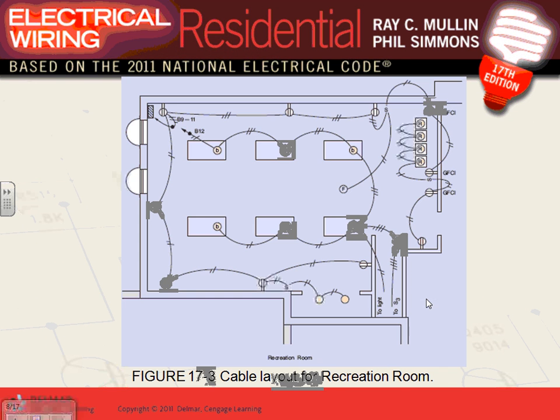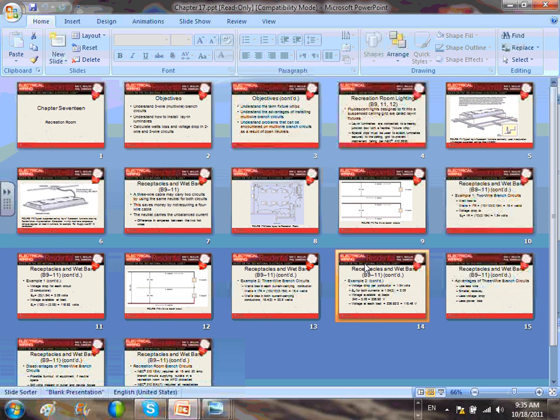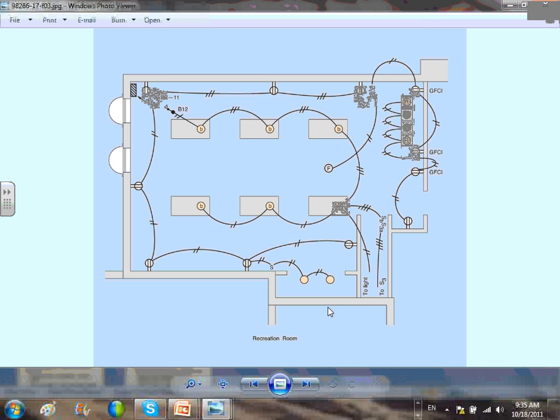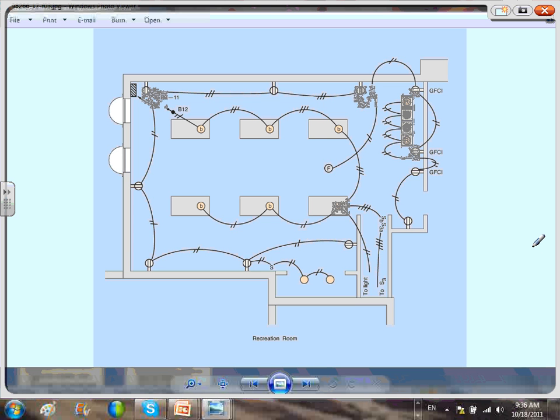directly. Let's go directly to the fixture. If you guys look at the way they did this recreational room, I'm going to go directly into the fixture. 17. Oh, here you go. If you guys look at the way they wire them, now, Rob, my friend, if I want to wire this room based on the code, how many circuits do I need? If you continue 10 or less receptacles in one circuit, that's all you need.